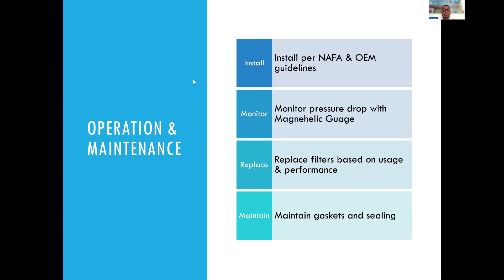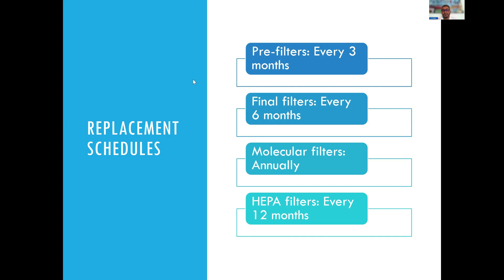Replacement schedules. Pre-filters should be changed every 3 months. Final filters should be changed every 6 months. Molecular filters should be changed annually, based on the condition of the carbon, if it's spent. And HEPA should also be changed every 12 months and tested at the same time. So what we're really saying here is you should do 2 full changes a year, but change your pre-filters 4 times a year.